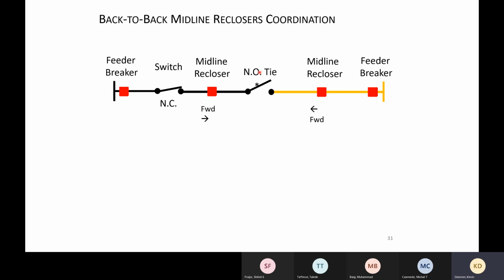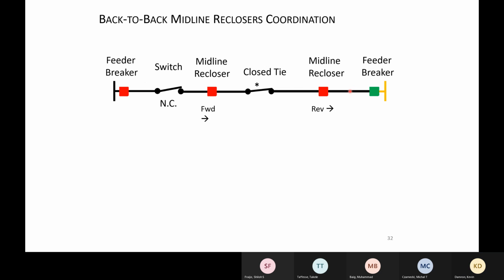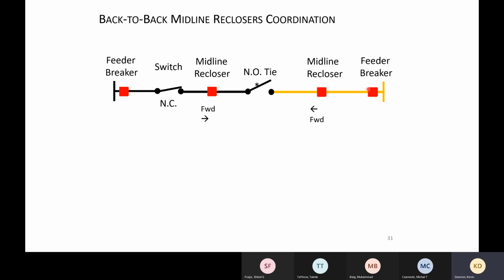So we started tying a lot of our feeders together with normally open ties. As I was saying, one of the advantages is if I had a fault here, I could open this breaker, close this switch, and carry all the load from the other substation. Now that affected the fact that normally on these two feeders, this was a forward direction. It was flowing from the feeder breaker to the recloser. This feeder was flowing from the feeder breaker to the normally open point, through its recloser.